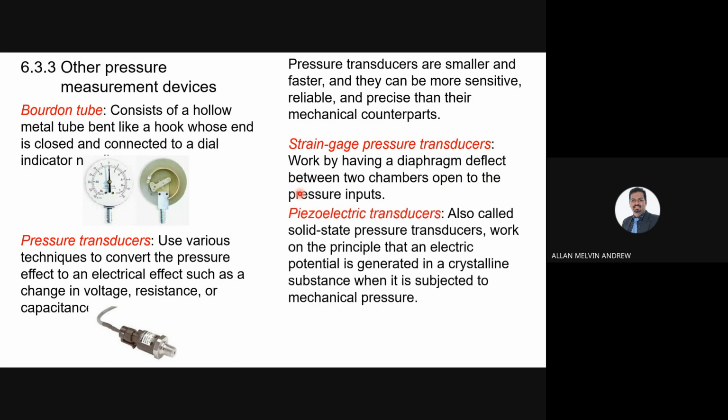Then we have piezoelectric transducers. Piezoelectric is more electronics. Also called solid state pressure transducers, they work on the principle that an electric potential is generated in a crystalline substance when it is subjected to mechanical pressure. So piezoelectric is more on the crystal.